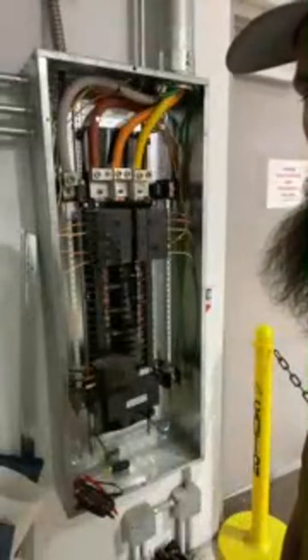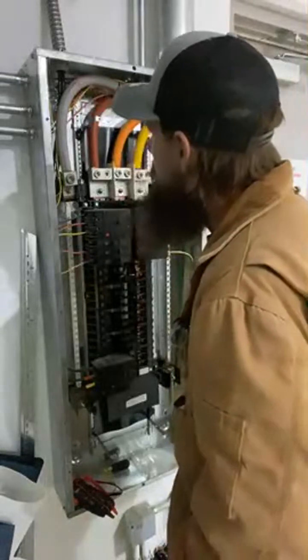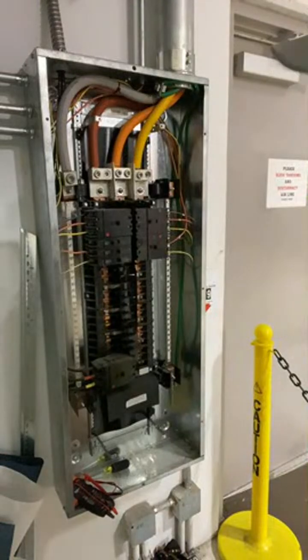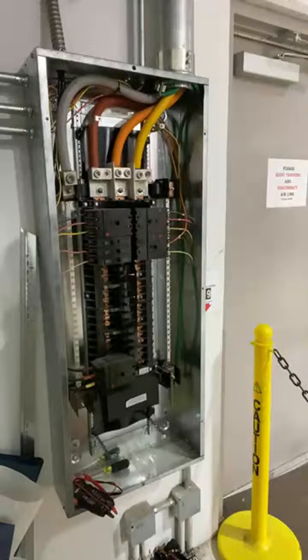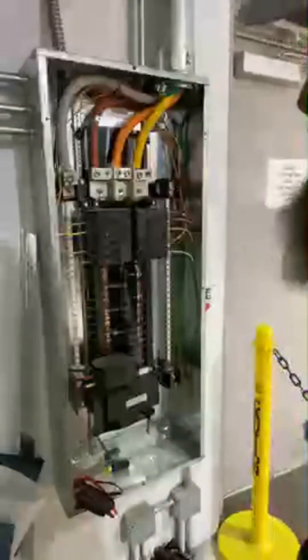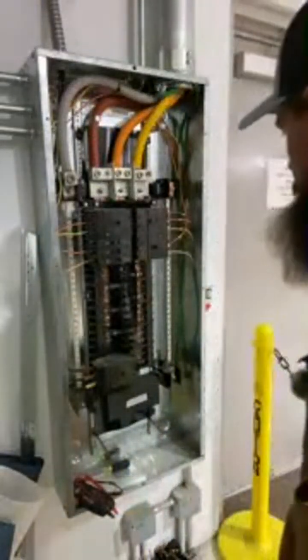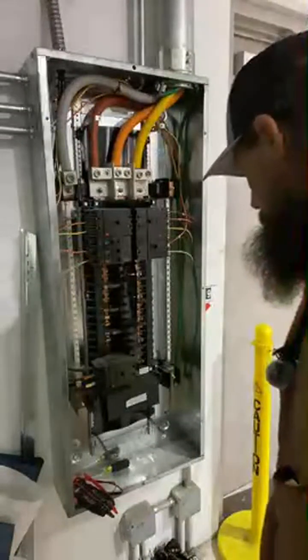Not exactly sure who made this panel up, but I know that's not 750, that's 600. Anyway, that 600 ain't easy to bend, but that looks like shit, kinda. But it be what it be. The more I look in this panel, the more it makes me cringe. I've got multiple grounds coming through one raceway, no nylon bushings on some things. Hell, one pipe's got 3 grounds coming through it. Wowzers. One doesn't have any grounds. It looks like that ain't no good.